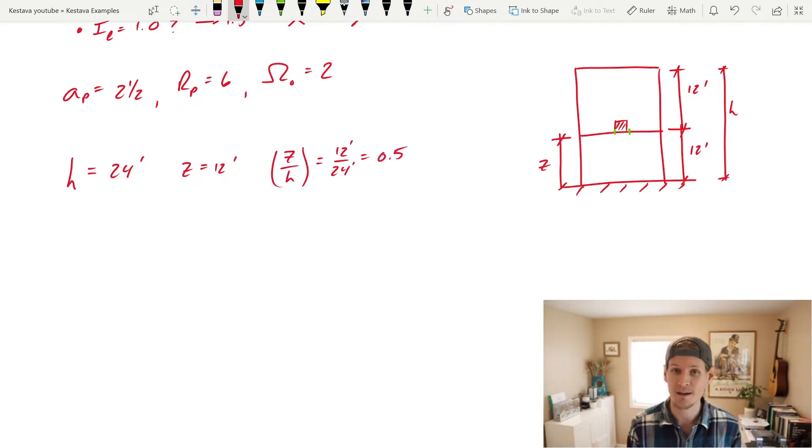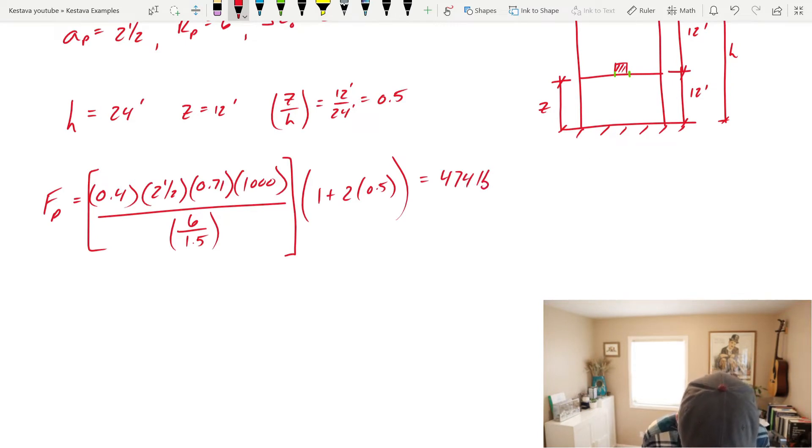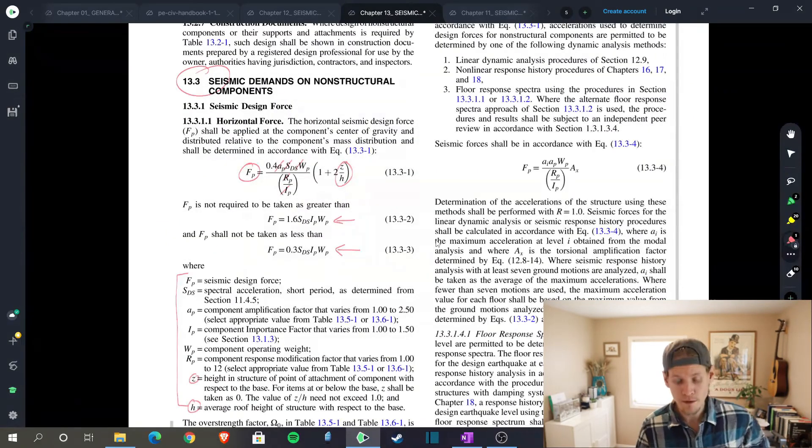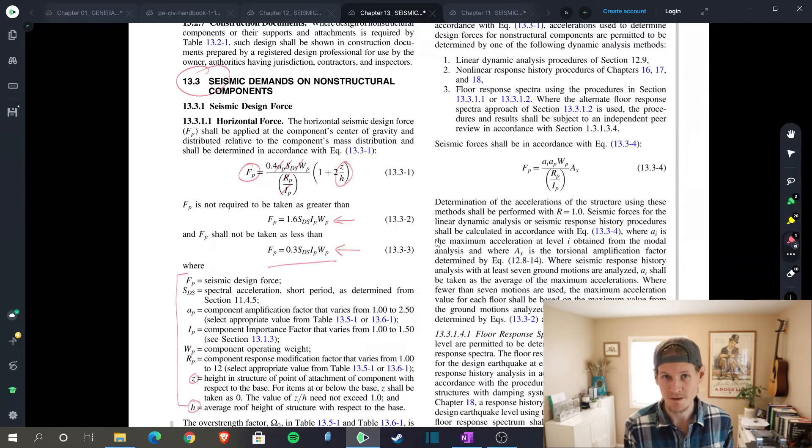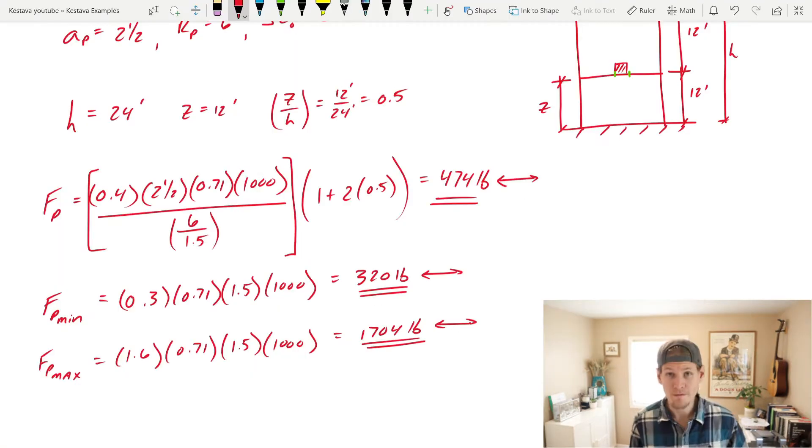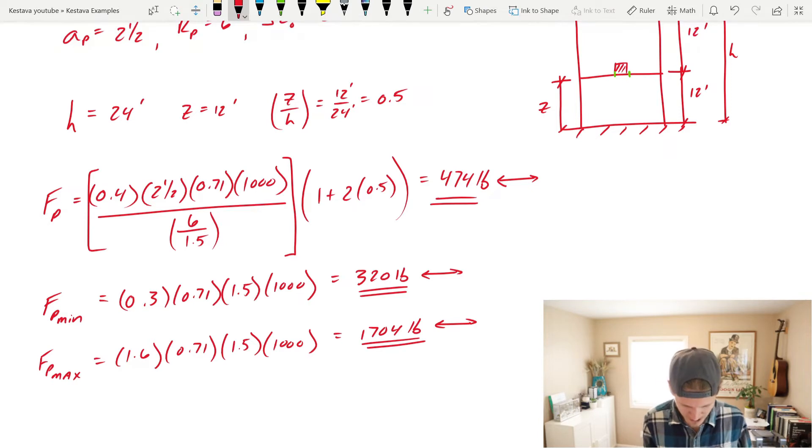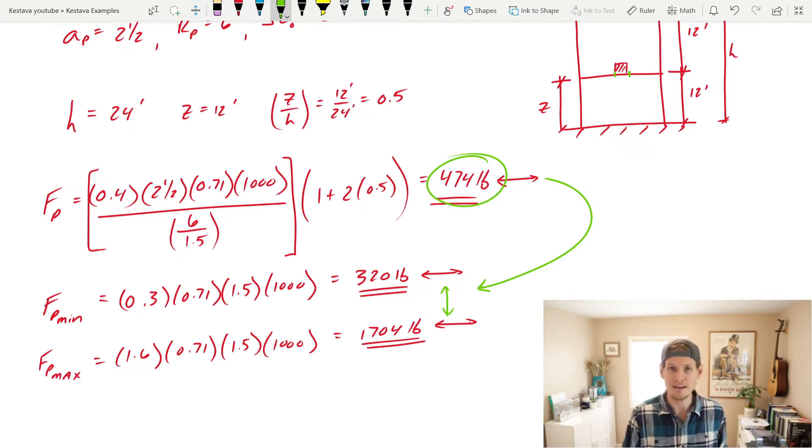Now we have all of our components. Plug everything in. All that gets is 474 pounds of lateral force in each direction. Fp min is 0.3 SDS importance times weight. And Fp max is 1.6 SDS times importance times the weight of your unit. Let's plug all that stuff in because we have everything. We have a minimum of 320 pounds and a maximum of 1,704 pounds. And what you do is you just need to make sure that your Fp value that I circled in green falls between these two values.